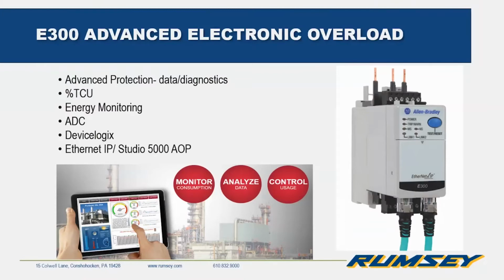utilization. When we think about overloads, a lot of times we think about current, and higher amperage is not a good thing. But what really destroys motors is actually the heat that the higher amperage causes. So this overload has a calculation that looks at what your full load amps should be, let's say 5 amps. And if the motor is running at 7, 8, 9, 10 amps, it does this calculation and gives you a percentage of thermal capacity that is used up.